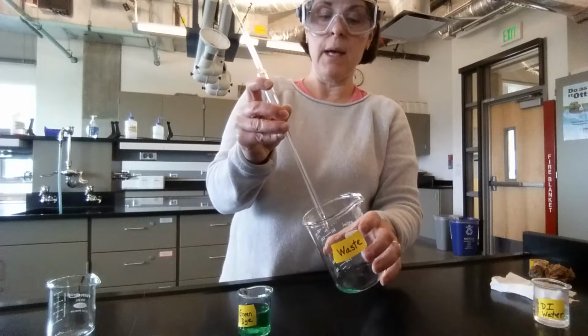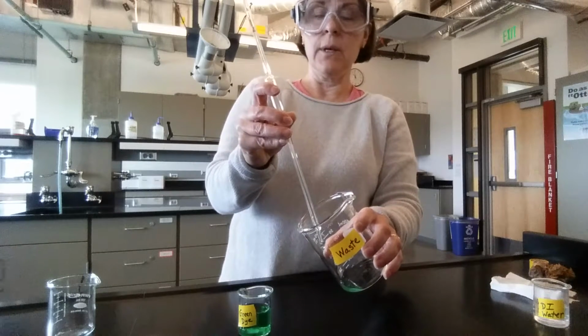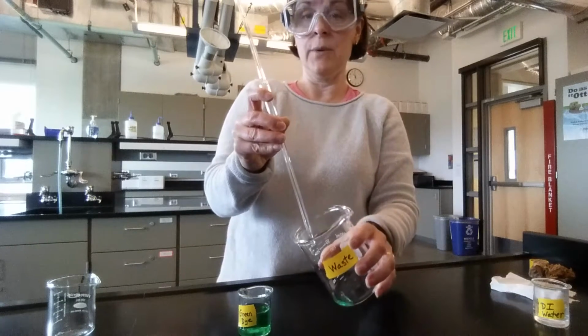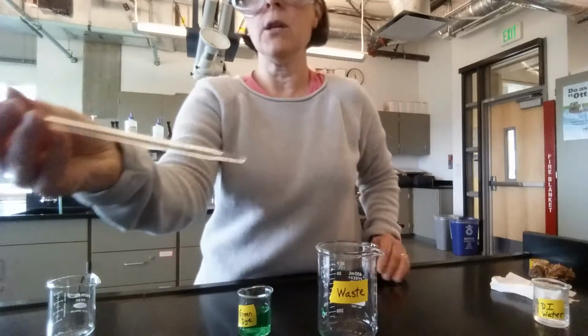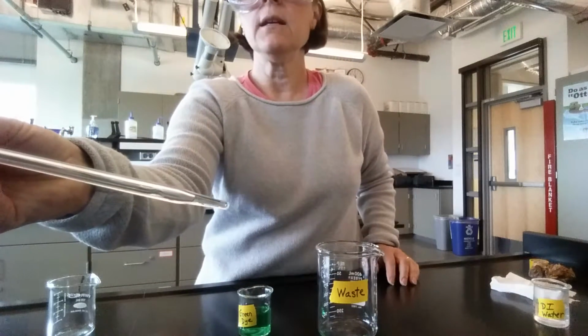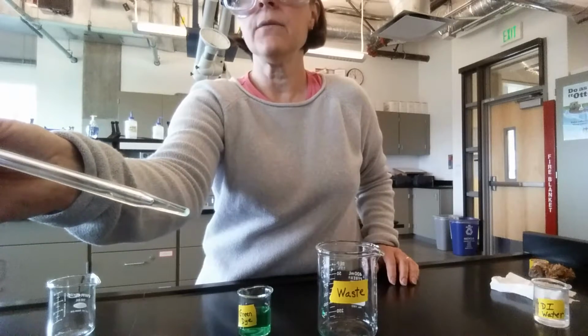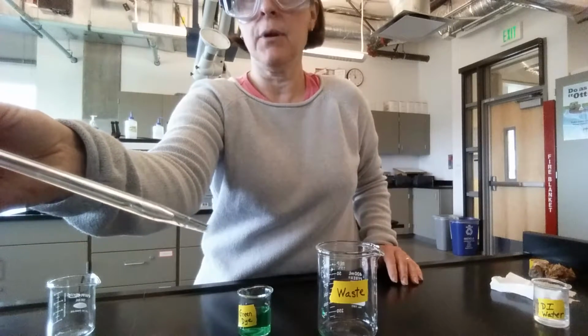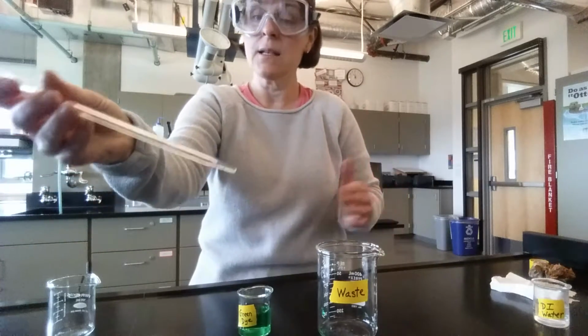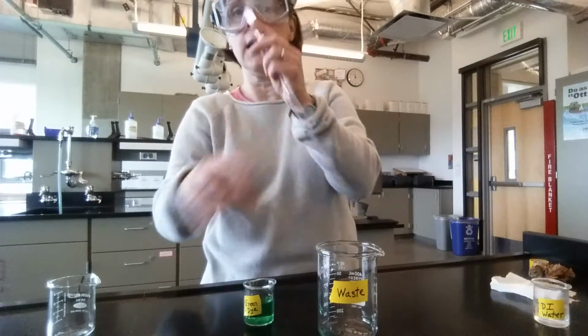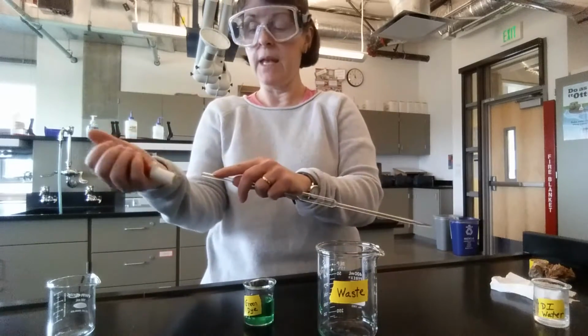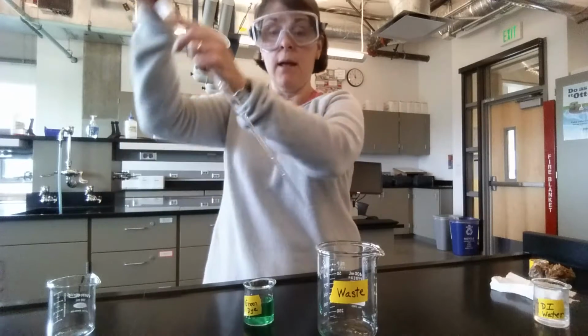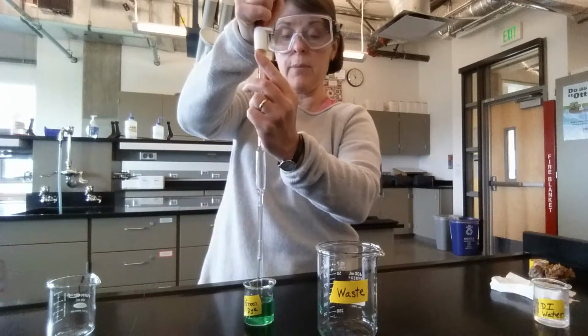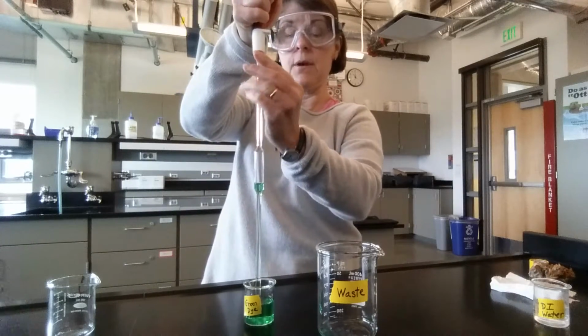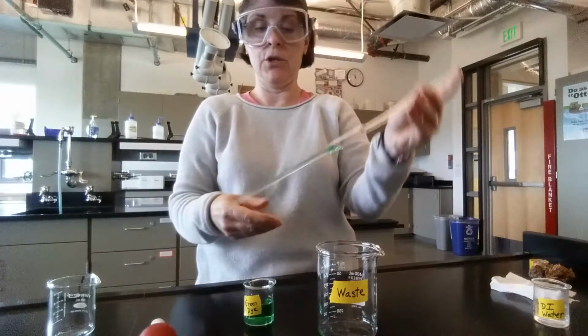Touch the tip of the pipette to the clean inside surface of your receiving vessel, and you may notice that there is a little bit of liquid left in the top or in the tip of the pipette. This is correct. Your pipette is calibrated to keep that little bit of liquid in the pipette. We're going to rinse our pipette 3 times with the solution to be measured.